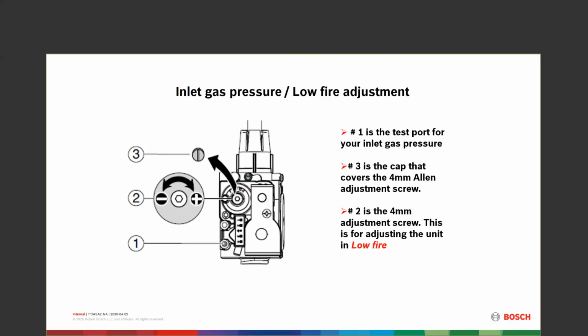So the gas valve, the way I remember it easily, gas valve is down low in the boiler. It adjusts low fire. The gas throttle is up high in the boiler. Gas throttle being high in the boiler adjusts high fire. That's my easy way to remember it. Gas valve's down low, it's low fire. And you have to adjust it that way. Low fire, adjust low fire. High fire, adjust high fire. That's it. We're done at that point. You're going to go through slow and easy, get things to adjust. A 1/16 of a turn can change you by about 0.1 on the gas valve.